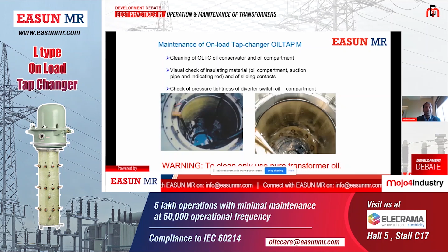We have to open the diverter switch here and open the cover, remove the diverter switch carefully, and then the next procedure will follow. You can see there is a huge sludge in the bottom. So that oil has to be removed. And most important, you can see here that the cleaning has to be done with good transformer oil. It should not be done with water or anything like Biodial or whatever. We should only wash with good oil so that the insulation level remains good.